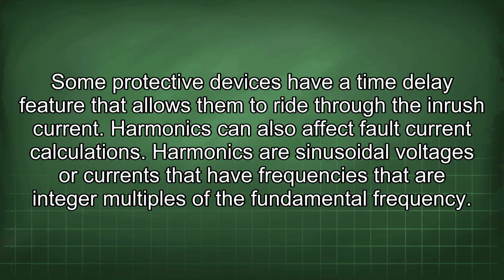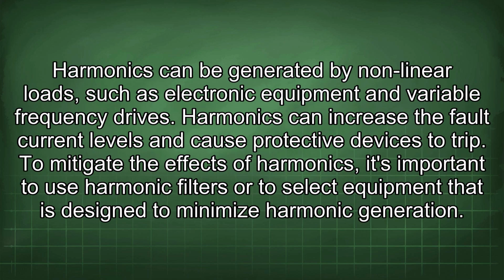Harmonics can also affect fault current calculations. Harmonics are sinusoidal voltages or currents that have frequencies that are integer multiples of the fundamental frequency. Harmonics can be generated by nonlinear loads, such as electronic equipment and variable frequency drives. Harmonics can increase the fault current levels and cause protective devices to trip.